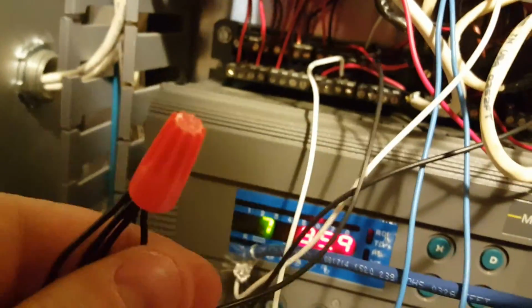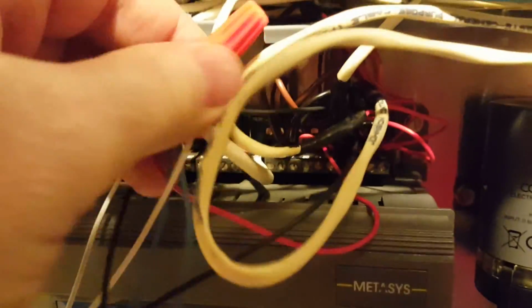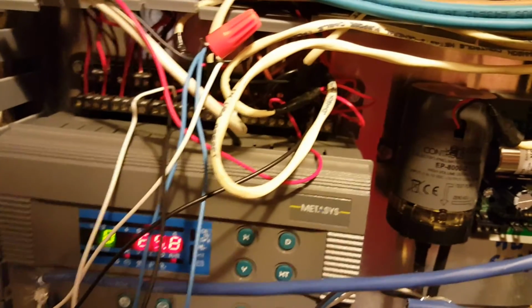That's our first steps. Now we need to get everything wired up. We have it here. It's not cleaned up very well. Since this is a 3-wire valve, you need to make sure that you connect both to your power supply, your common, as well as your analog output common, and then also connect to your AC source as well as the analog outputs from your DX9100. The white wire that is in my hand is one of the outputs, and the black wires are going to the analog output common as well as jumpered over to our AC common for this particular device.